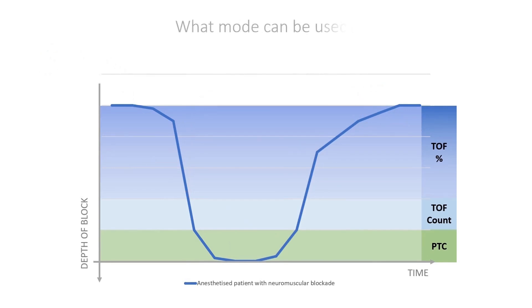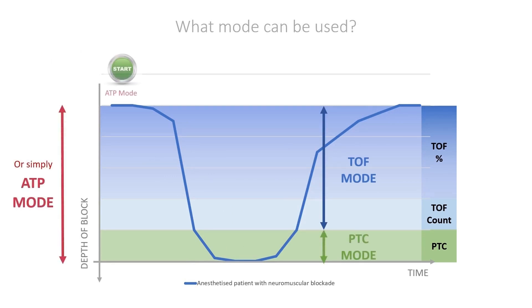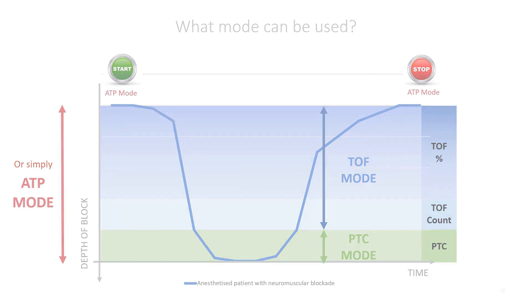The autopilot ATP mode is a very simple and efficient way to monitor the patient's paralysis without having to change the mode manually. You can choose this mode at the beginning of the intervention and let it run until the patient has reached the recovery phase.